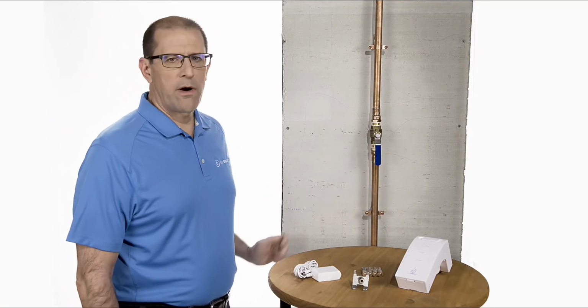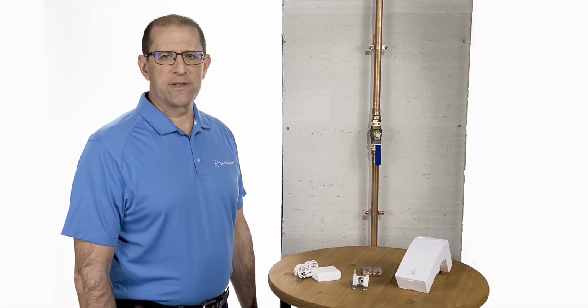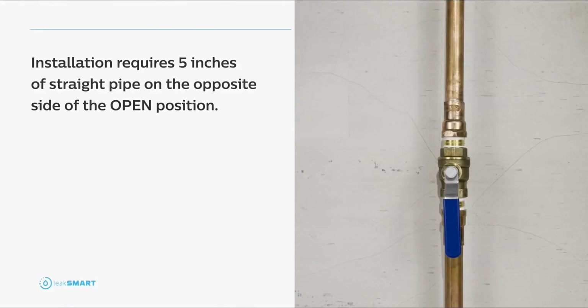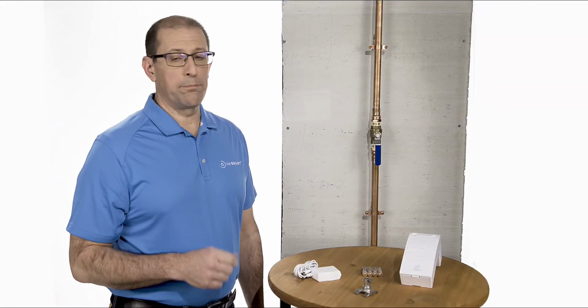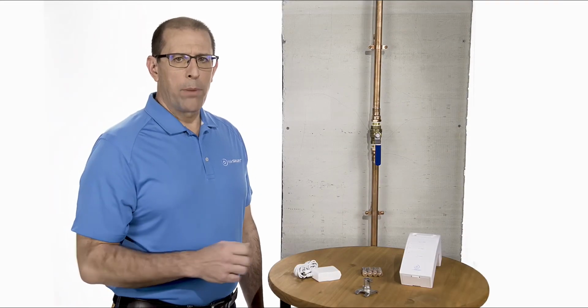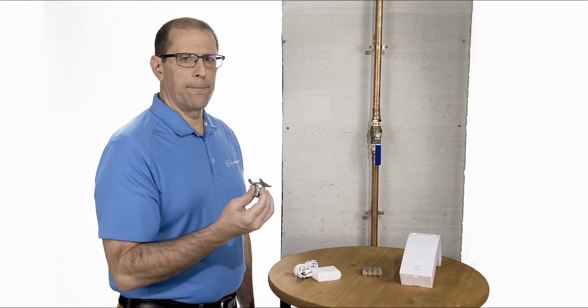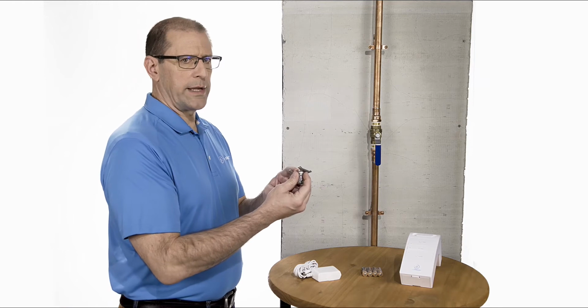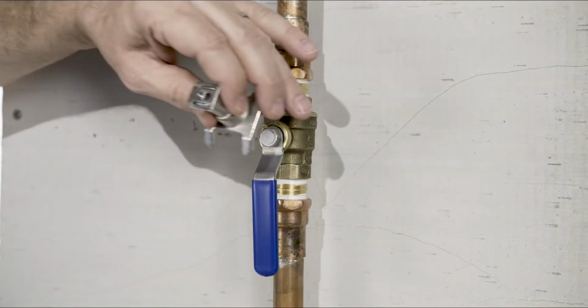You will need to make sure there are 5 inches of clearance opposite the handle. Installation requires 5 inches of straight pipe with no obstructions or bends on the opposite side of the open position for the snap clamping mechanism. You can install the LeakSMART Snap vertically or horizontally, but not upside down. A ball valve adapter comes with the snap kit. The ball valve adapter can fit a small or large handle. Make sure the adapter has a snug fit.